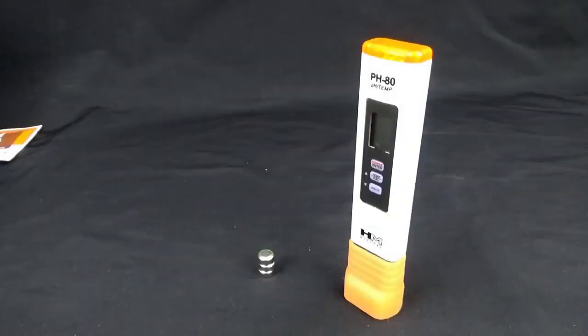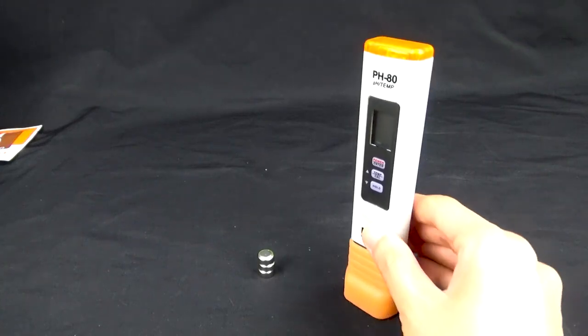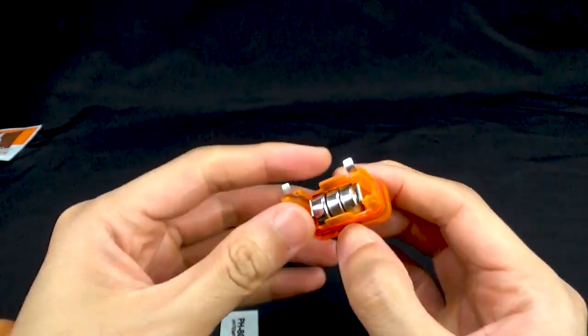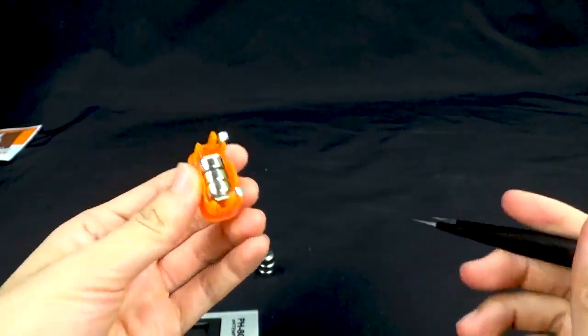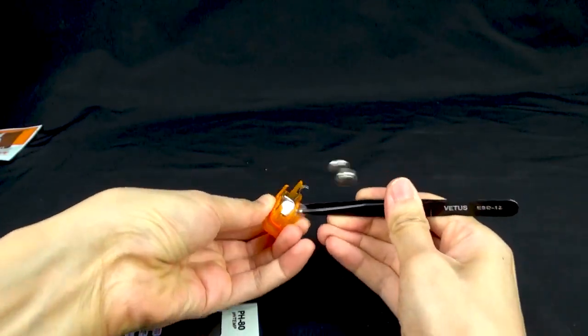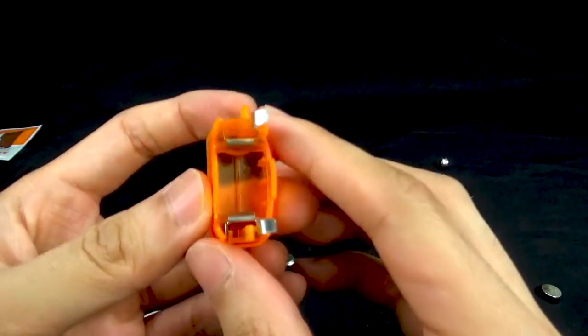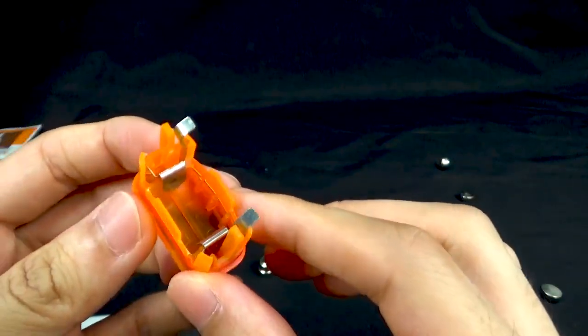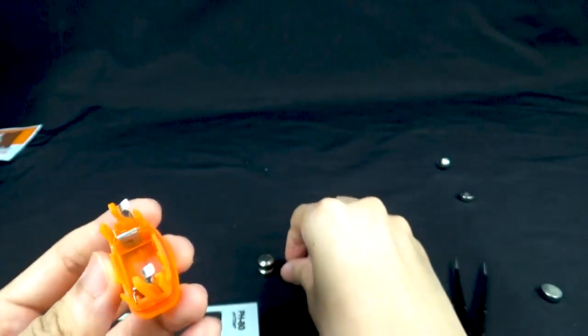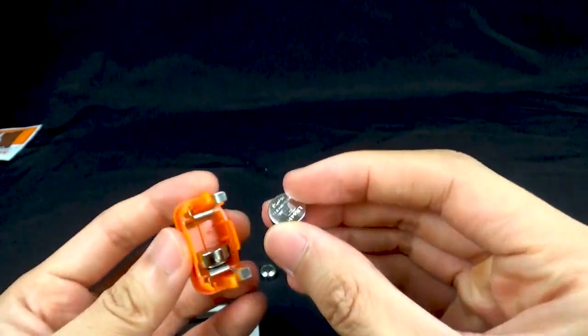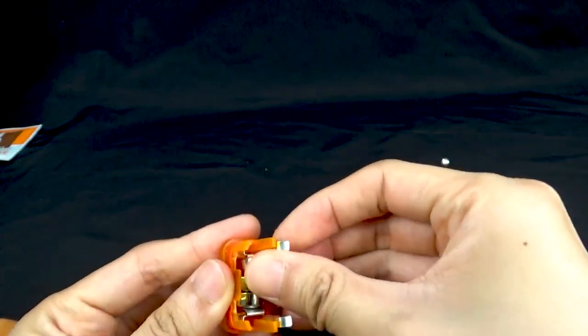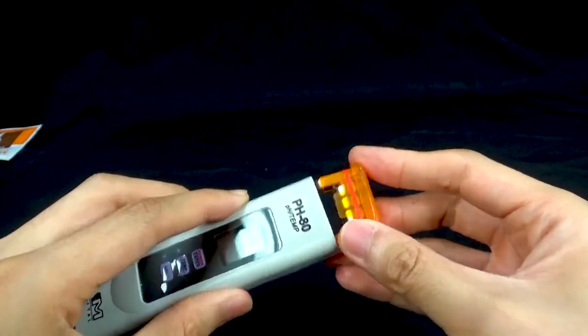When the meter displays a flashing battery symbol, it indicates that your batteries are becoming weak and should be replaced soon. The meter uses 3 LR44 button cells. To change the batteries, pull out the orange battery compartment. Remove the 3 existing batteries. Insert new batteries following the direction shown inside the compartment. Remember, the flat side of the battery is the positive side. Close the battery compartment securely, ensuring it is tightly closed.